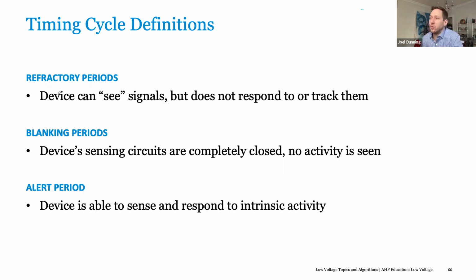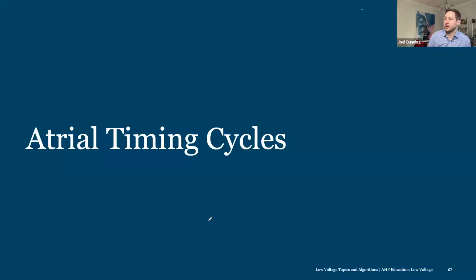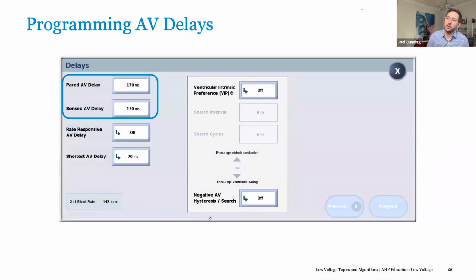Refractory periods is when the device is able to basically observe a signal, but it doesn't respond to them. Blanking periods are when the device is completely blind to any kind of signal that could be occurring. And then alert periods is when the device is able to sense an intrinsic activity and respond to it appropriately. So just keep that in mind as we jump into this. So the timing cycles are broken up between atrial and ventricular timing cycles. You have your initial AV delays, which is the time between an atrial event and a ventricular event.